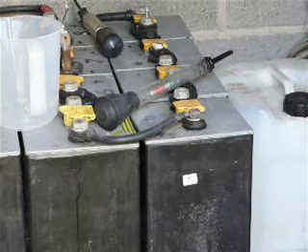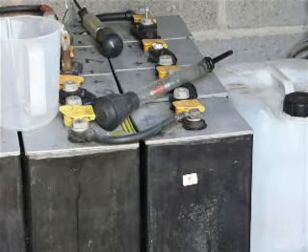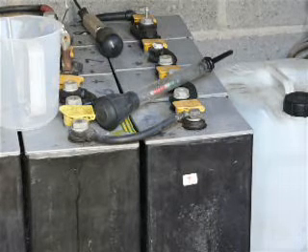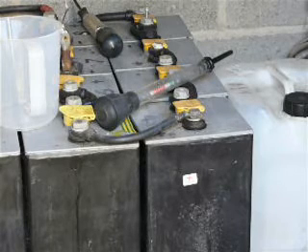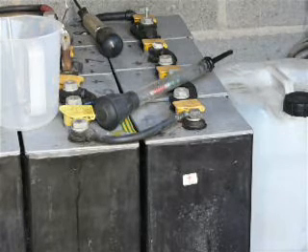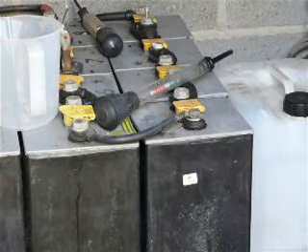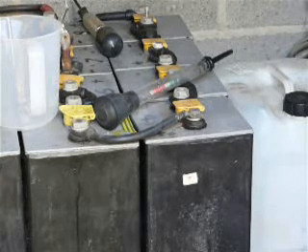This is not the only reason for not leaving batteries in a discharged state. There is also the fact that further damage will be caused if you try to take further power from the system. And also, when the acid is very weak, it can freeze in bad winter weather. This, of course, creates further irreparable damage.